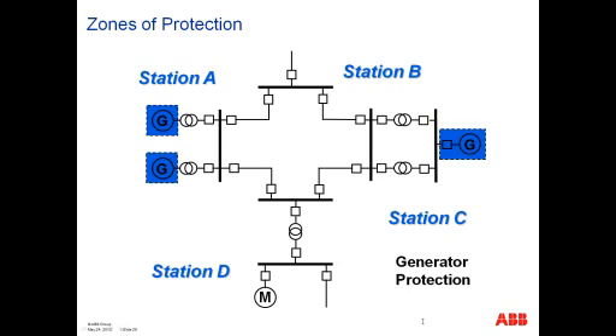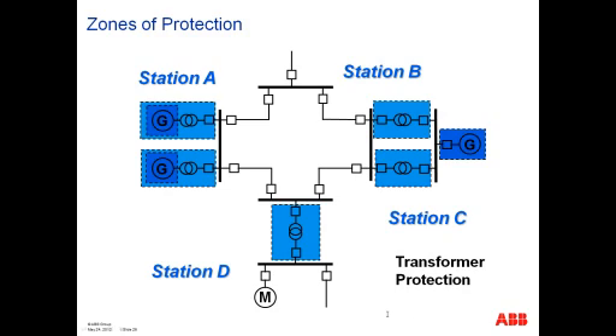If it's a generator that's connected to a breaker through a transformer, it would trip the transformer breaker on the high side. Then we add the next level of protection, which would be the transformers. And as you can see, the transformers would either have a breaker on each side to isolate problems, or in the case on the left, where the generator and transformer are all in one zone.